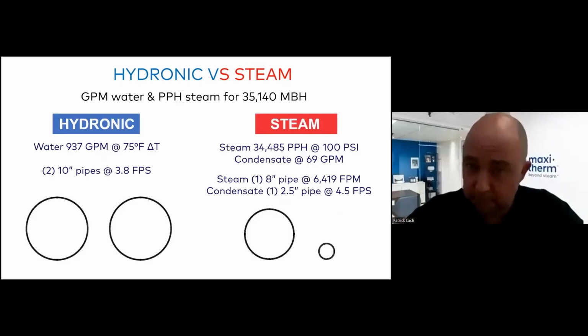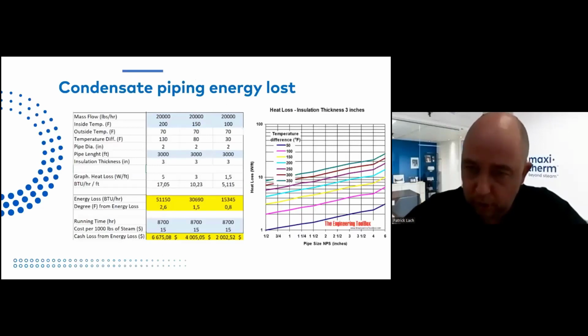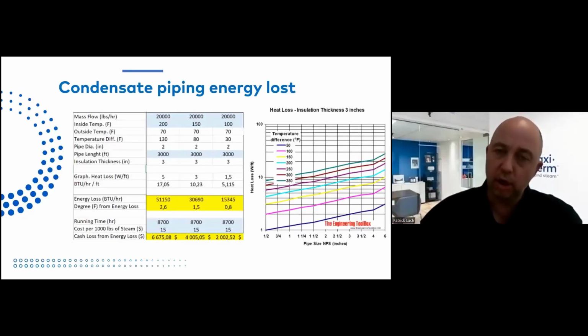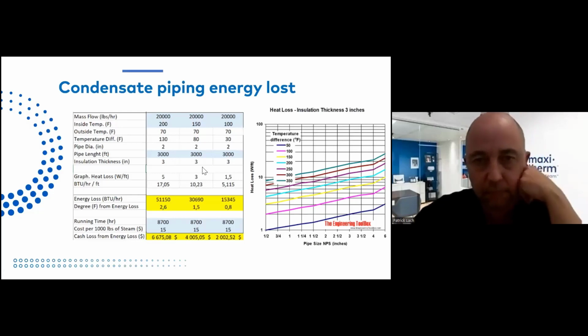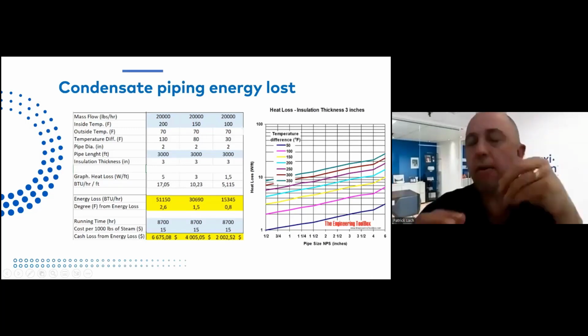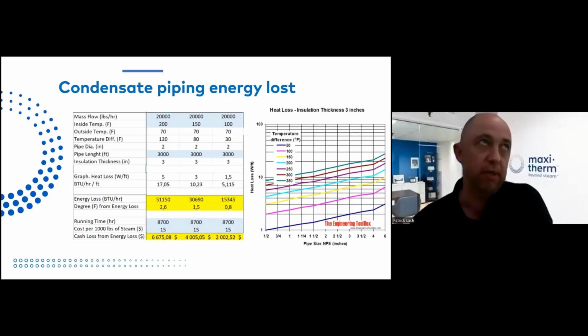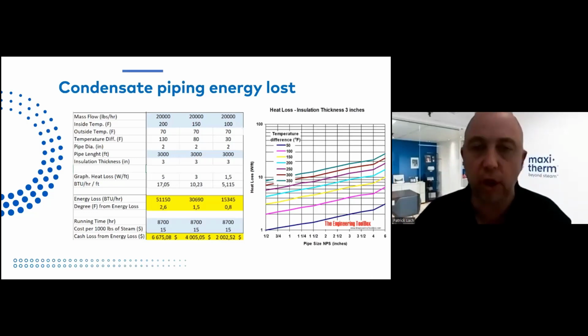The piping, steam piping will be a little bit smaller, and condensate piping will be much smaller. Temperature. When you return high temperature condensate, you have more heat loss than low temperature. So this table here shows, based on 20,000 pounds per hour of condensate back, temperature of the condensate, average temperature condensate here, right? Outside temperature, like room temperature, basically, here are the savings that you can make by having lower temperature condensate returning. It's not big, but I know it's part of the reasons why people consider hot water versus steam, because steam loss, there isn't.